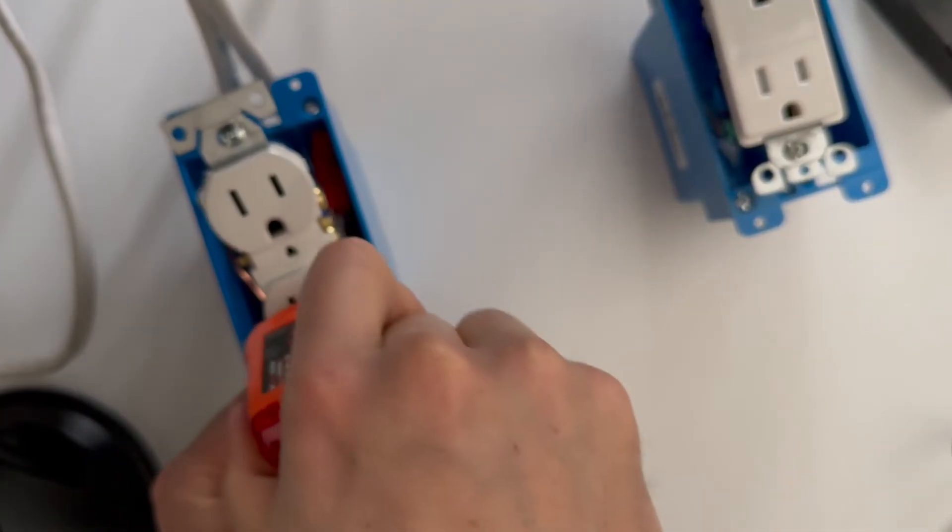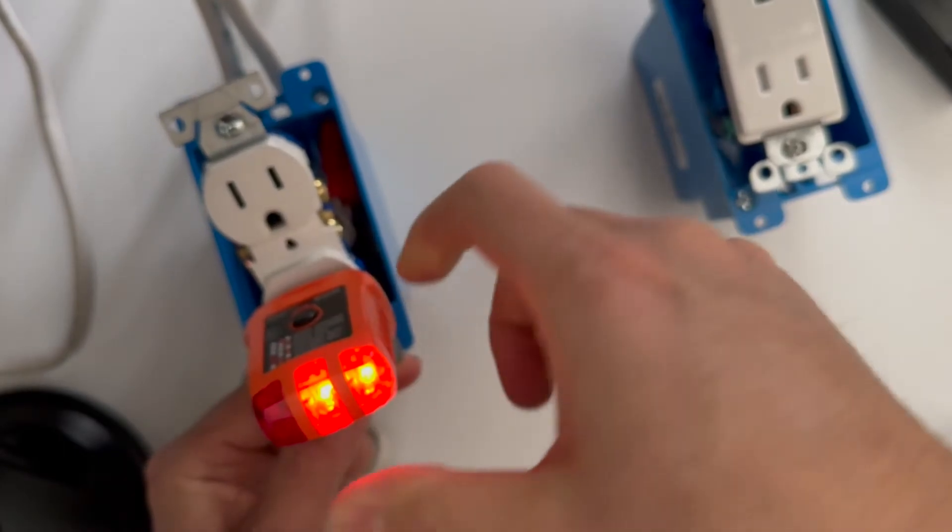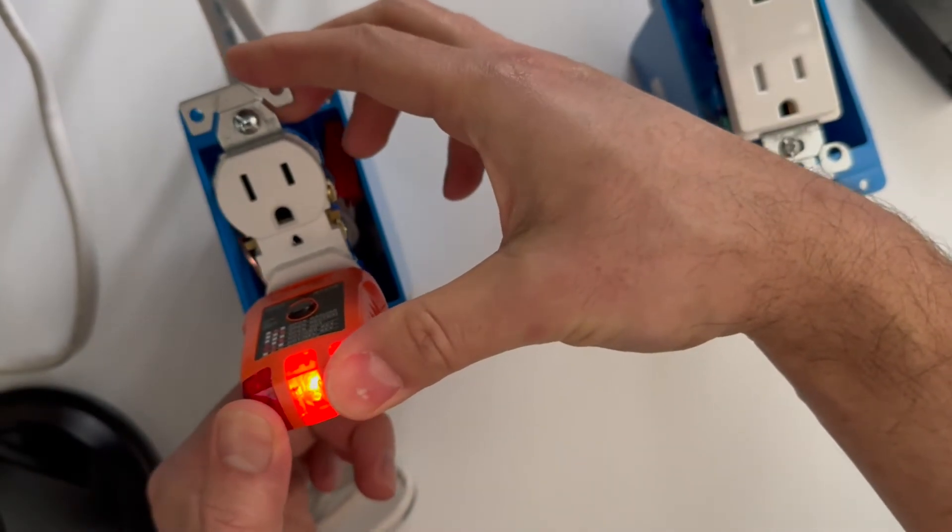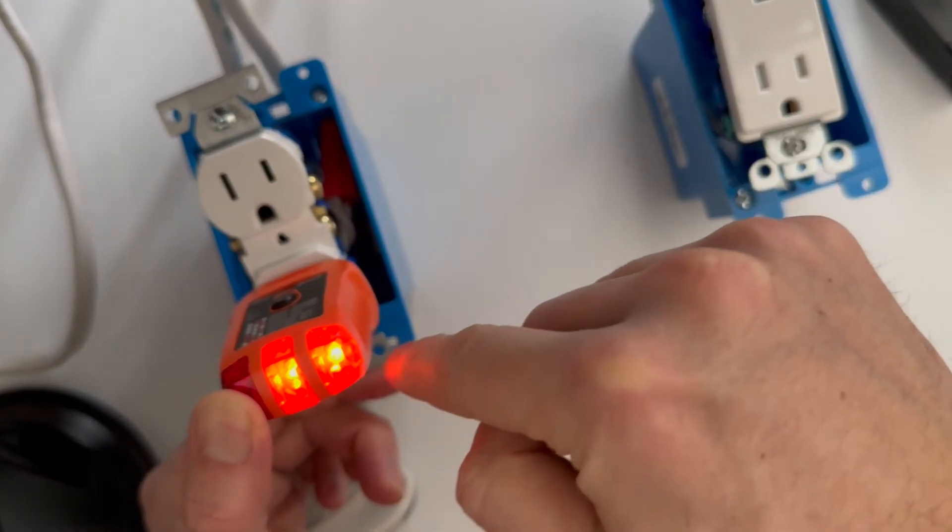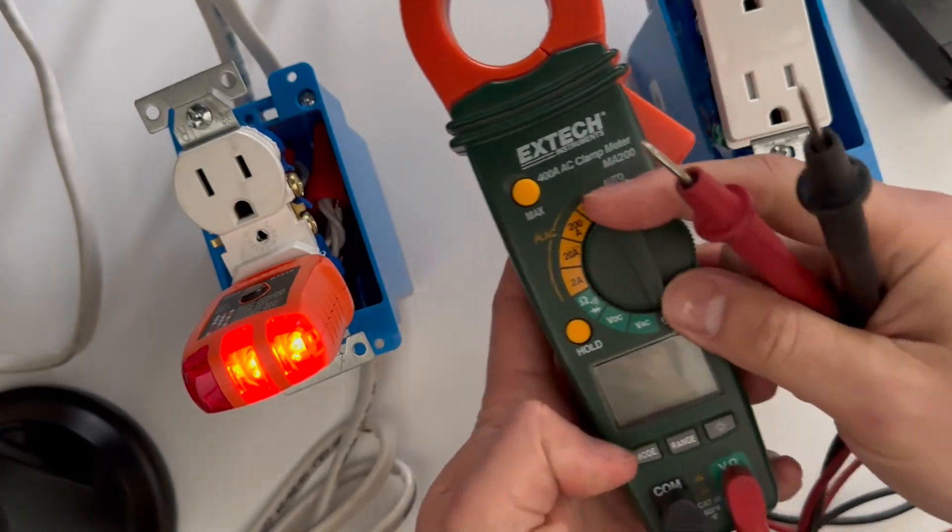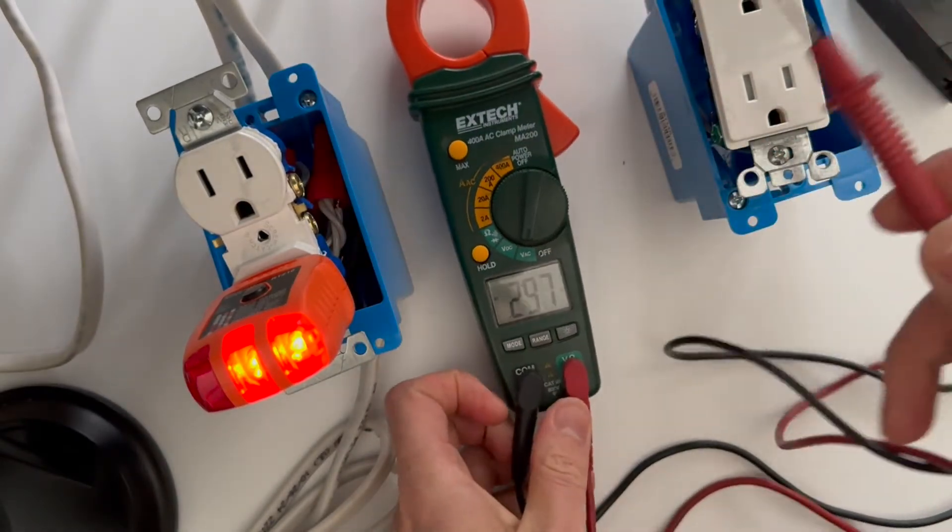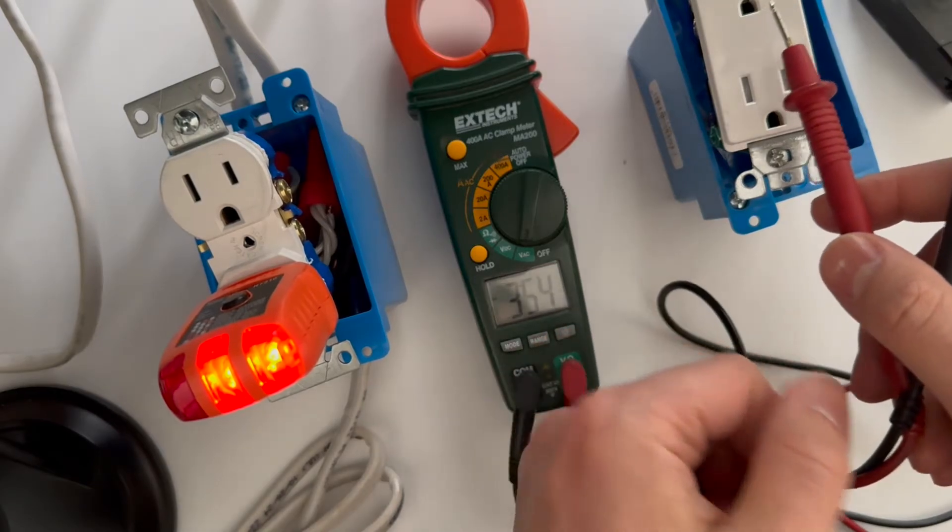In most cases, a lot of people just ignore the working outlet, but this is where your problem could be because these outlets are wired in a daisy chain. What I do is I pull out each outlet and I use a voltmeter to test the voltage.